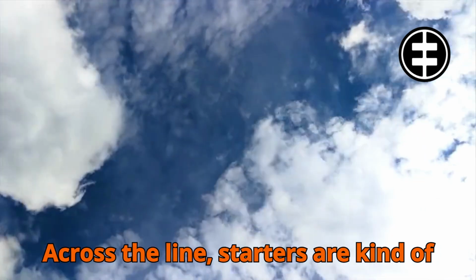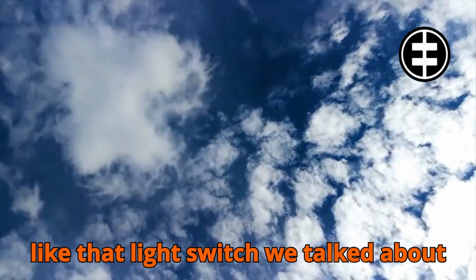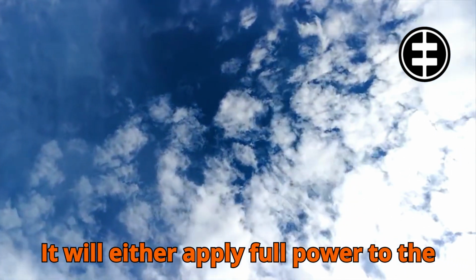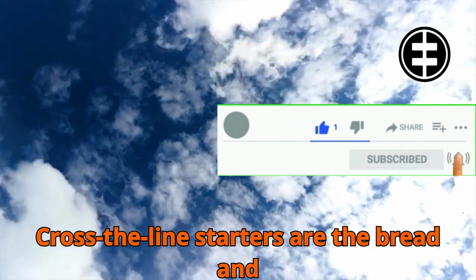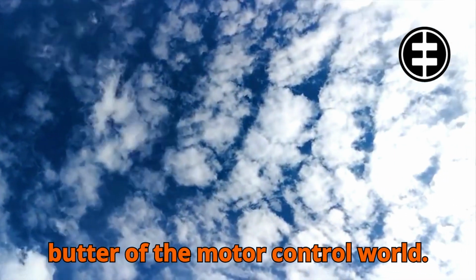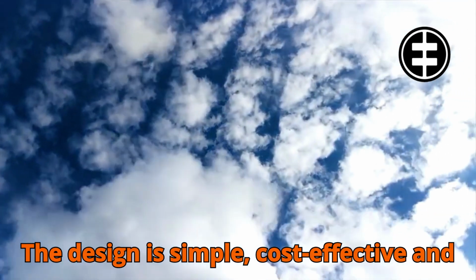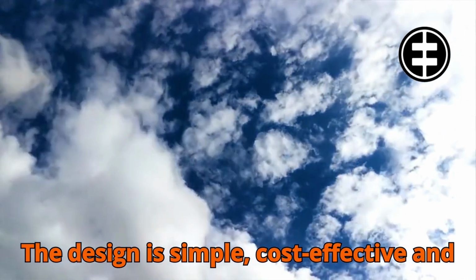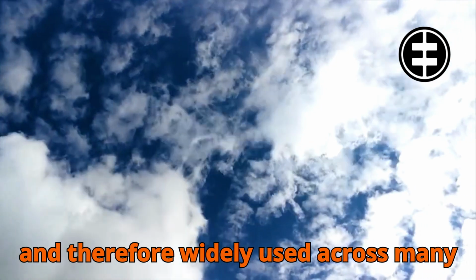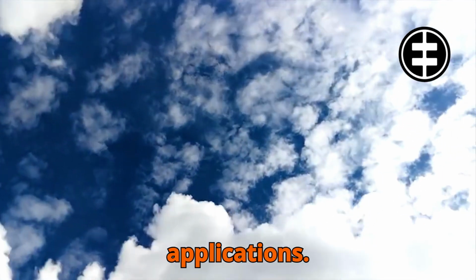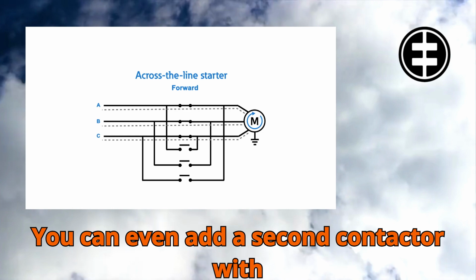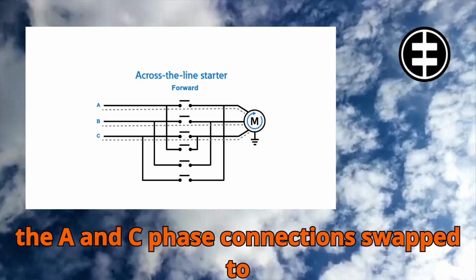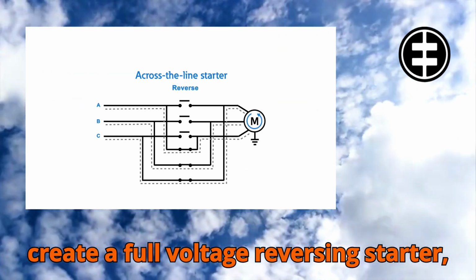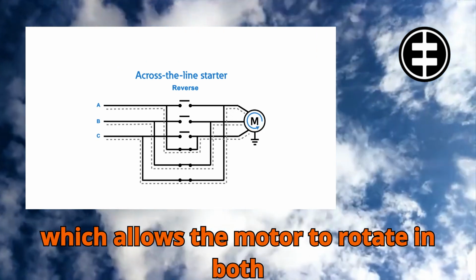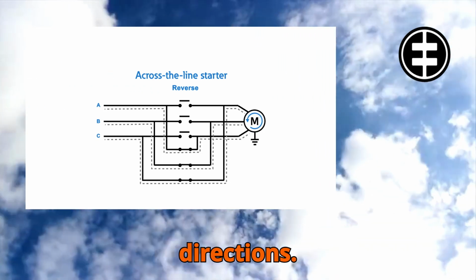Across-the-line starters are kind of like that light switch we talked about earlier. It will either apply full power to the motor or none at all. Across-the-line starters are the bread and butter of the motor control world. The design is simple, cost-effective, and reliable, and therefore widely used across many applications. You can even add a second contactor with the A and C phase connections swapped to create a full-voltage reversing starter, which allows the motor to rotate in both directions.